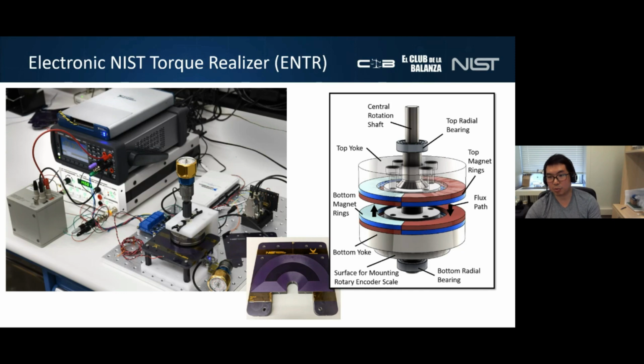And the end user can directly plug an analog torque watch, like you see here, to the ENTR to calibrate it. A pair of rare earth magnet rings generate the magnetic field and are mounted to a drive shaft and interact with a D-shaped coil, which is manufactured on a stack of printed circuit boards. The current version of ENTR rotates about a pair of very slick ceramic bearings, but its internal friction is what's limiting us from getting to that level. We have plans to design version 2 using a rotary air bearing, which we've already acquired.